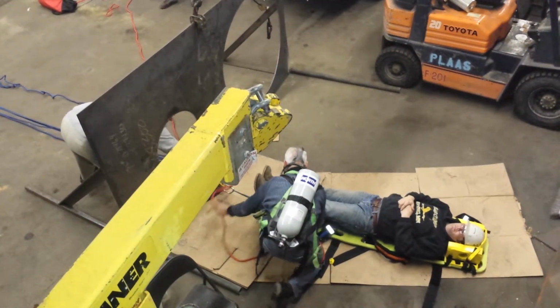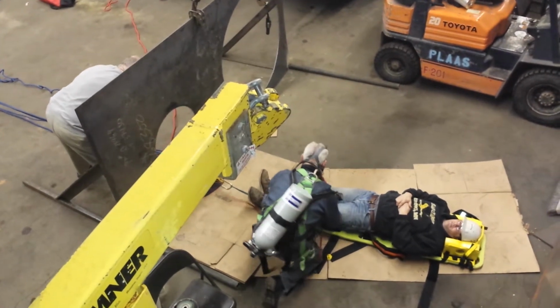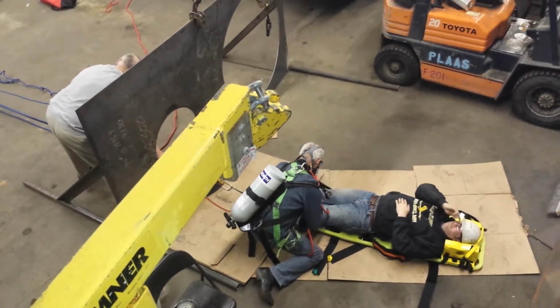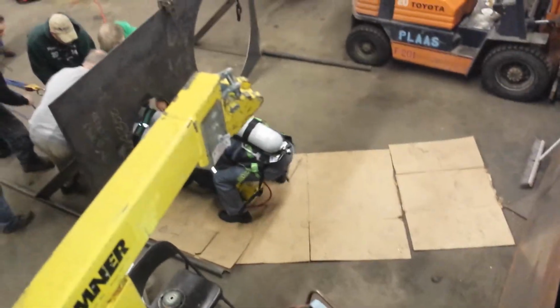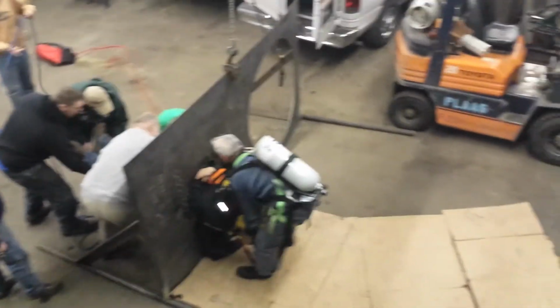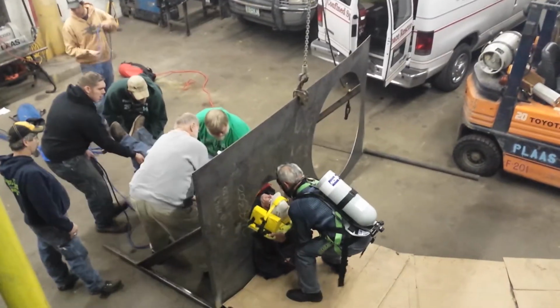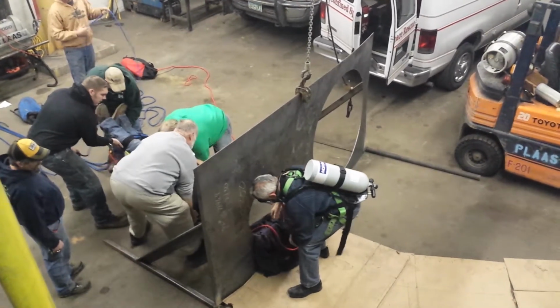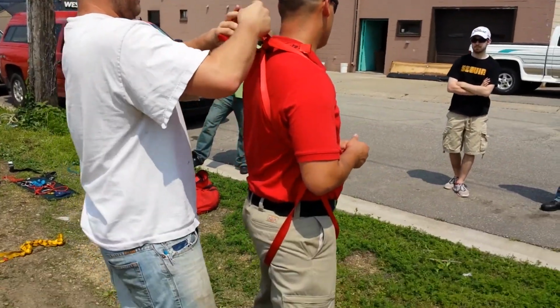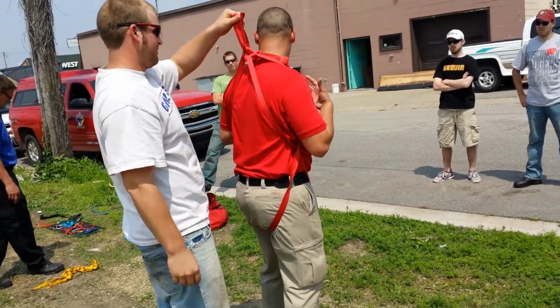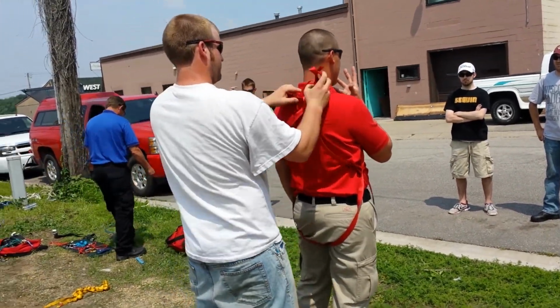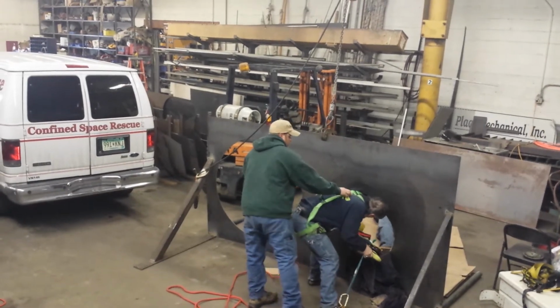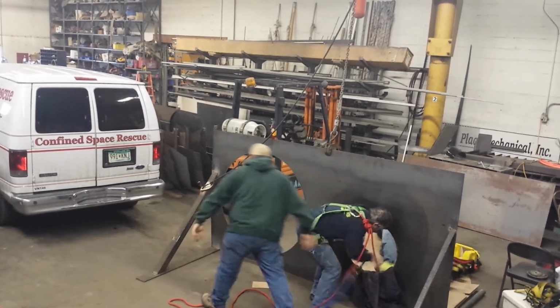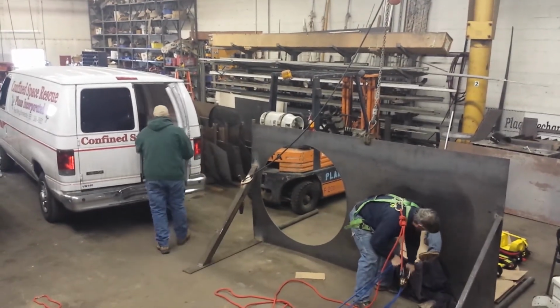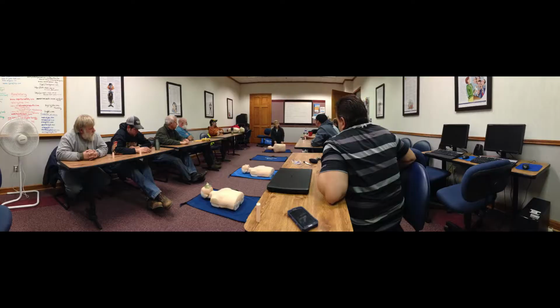Local emergency rescue teams shall be trained to perform the assigned rescue functions and have received the training required of authorized entrants. They shall also practice making permit space rescues at least once every 12 months by means of simulated rescue operations in which they remove dummies, mannequins, or personnel through representative openings and portals whose size, configuration, and accessibility closely approximate those of the permit spaces on site. At least one member of the rescue team shall maintain current certification in basic first aid and cardiopulmonary resuscitation (CPR) skills.